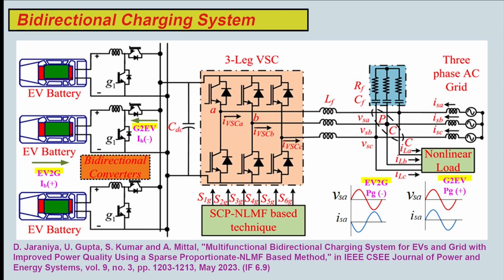After this DC bus, there is a 3-leg voltage source converter which has 6 switches. We have assumed a 3-phase system, so a 3-leg voltage source converter has to be utilized. Then we have an interfacing inductor, and some filtering units in the form of filter inductor and RC. The point of common coupling is where we can connect onboard chargers, residential loads if required, and then connect this system with the 3-phase grid.